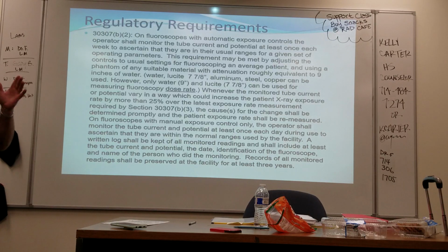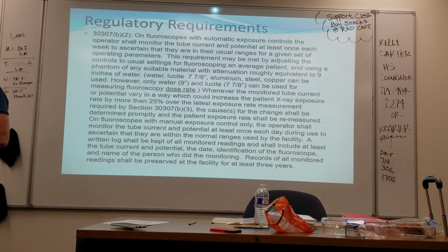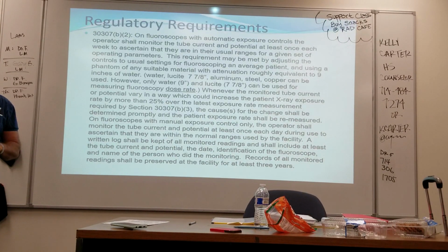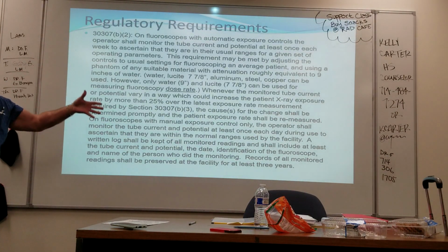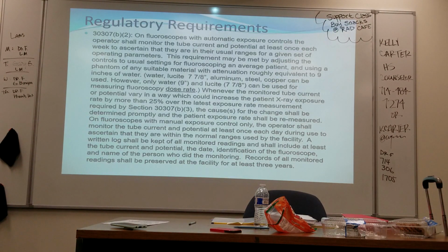Most facilities, what they do is they have the nighttime tech do it because there's very, very little to do. And in many facilities, even though there's equipment in surgery and orthopedics and the cast room and the ER and other places, a lot of hospitals look at it and say radiology is responsible for all of it. So that's what the night tech in many places gets to do, is they get to go do the weekly checks everywhere. So, but that's a state requirement. Simple test to do.